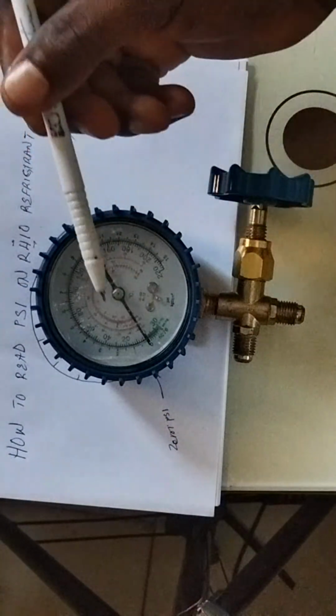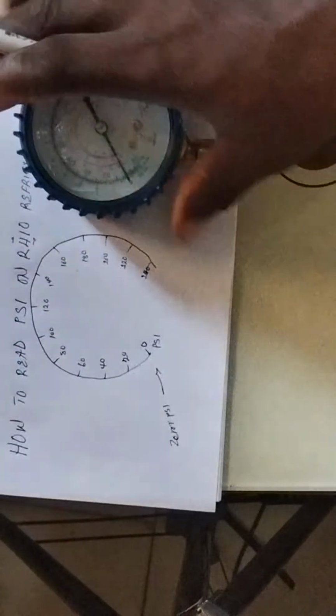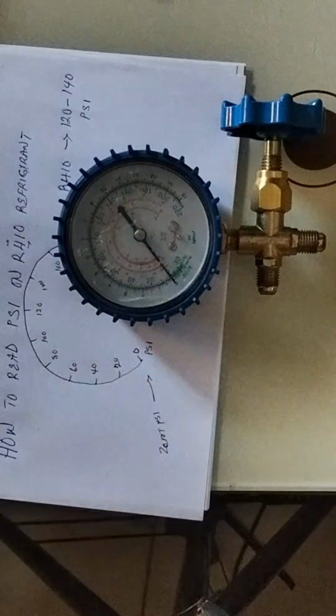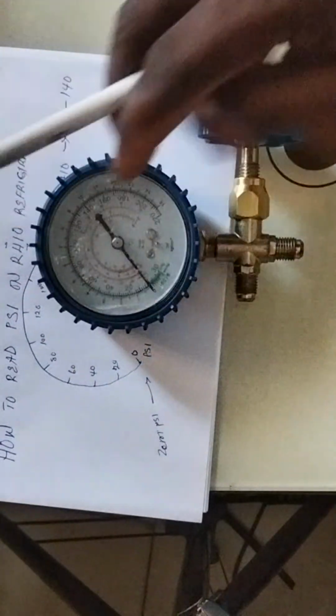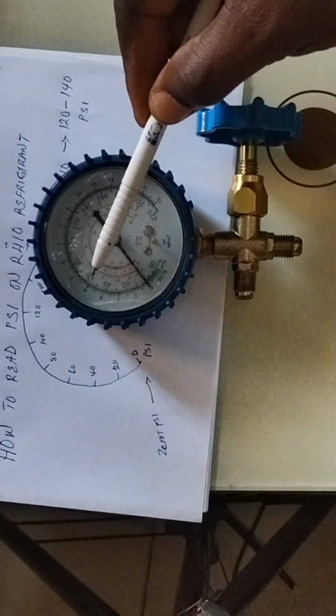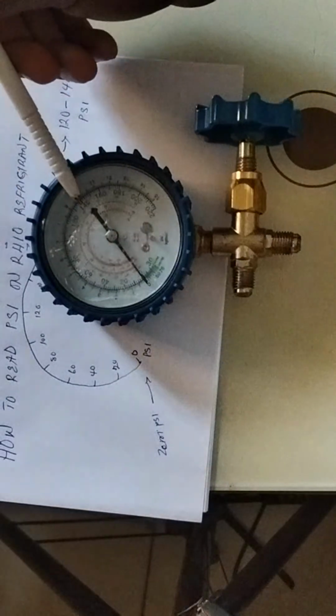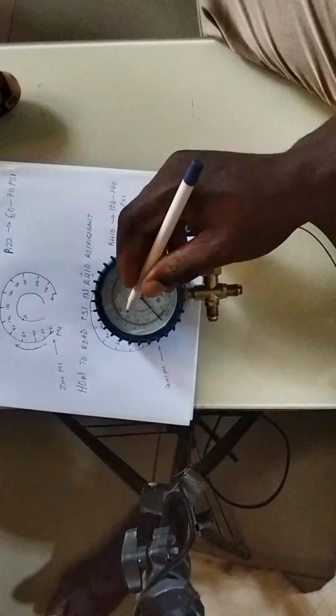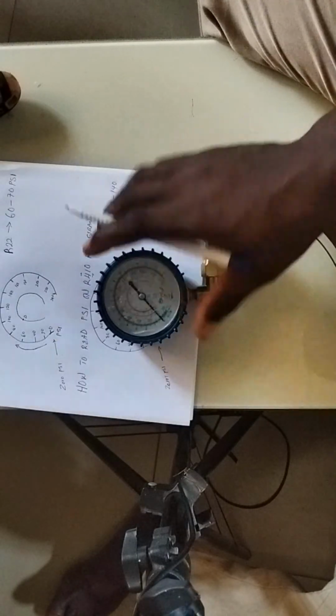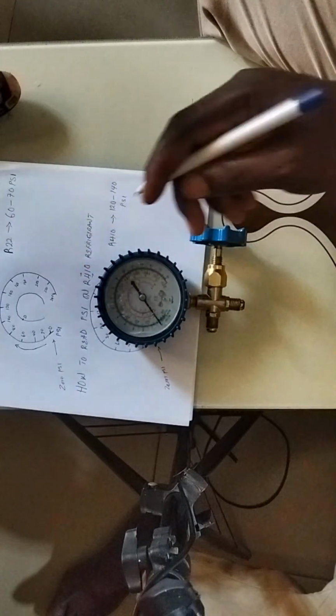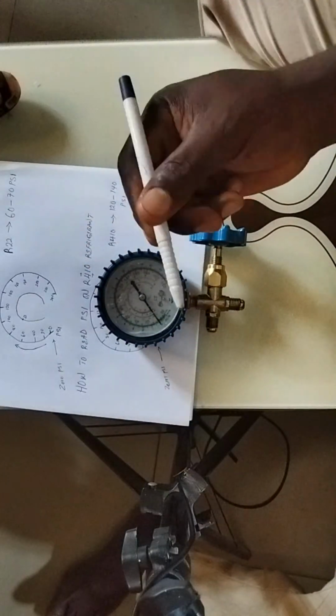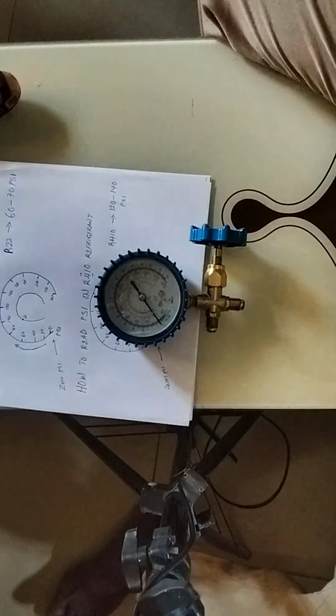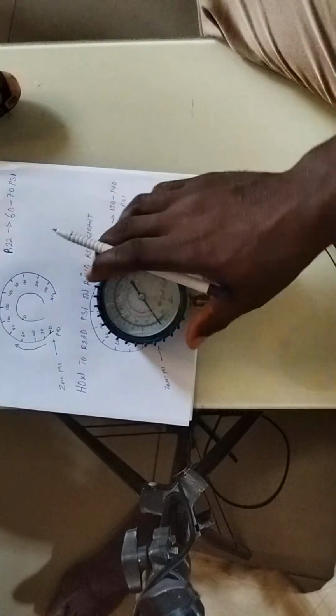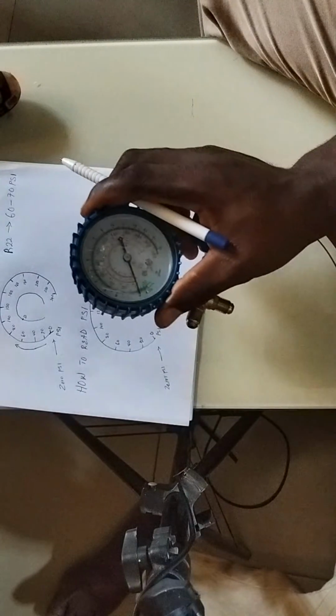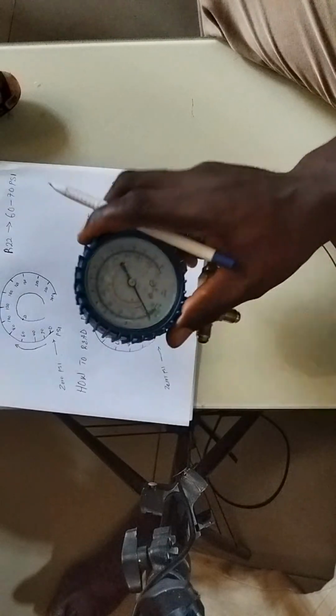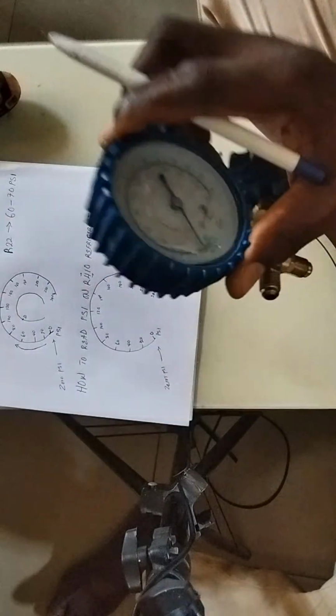If you have a refrigerant already on the system, like we are talking about R410 refrigerant now, and as you set up your gauge, you see that the refrigerant is at 60 psi instead of 120 or 140 psi. If it's reading at 60 psi, you allow that gauge to be on the system for about 20 to 30 minutes. 20 to 30 minutes will help you to notice if there is actually a leakage on that system. This is while the AC is still running, while the AC is still working. I don't know if you get the point. Either when the AC is still working or when the AC is not working, once you just set up your gauge, you know what you are doing.